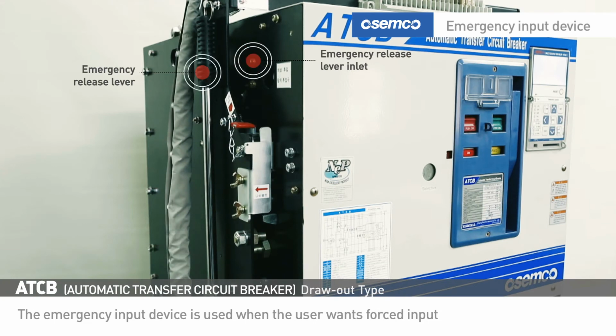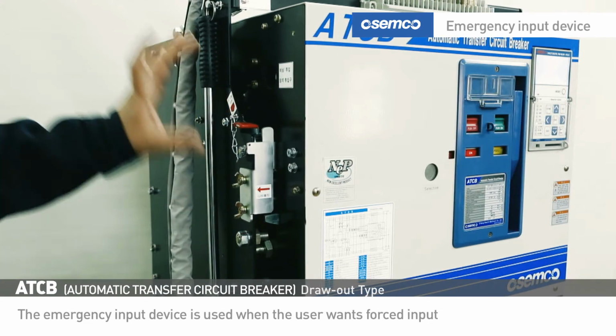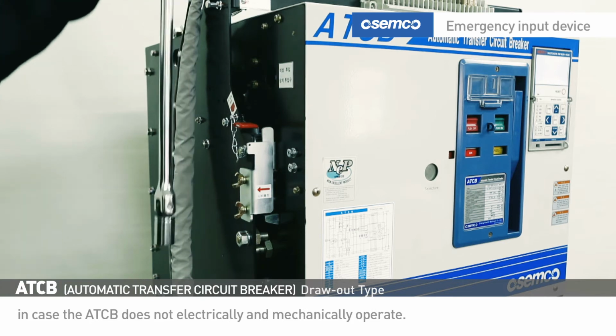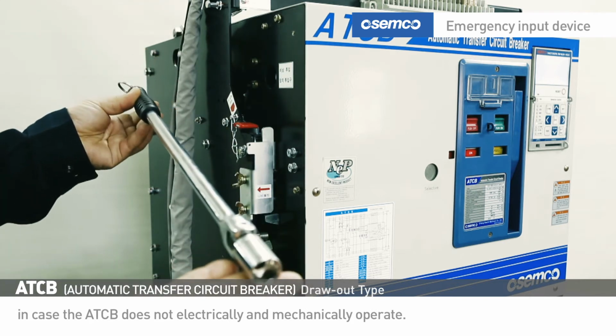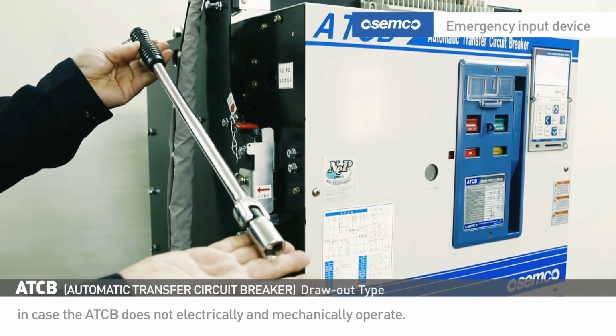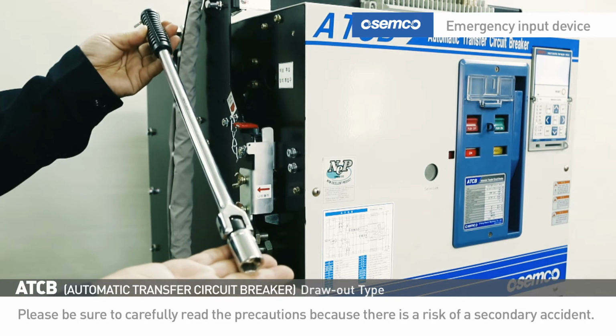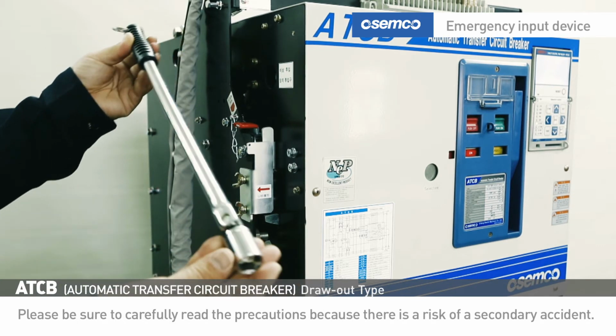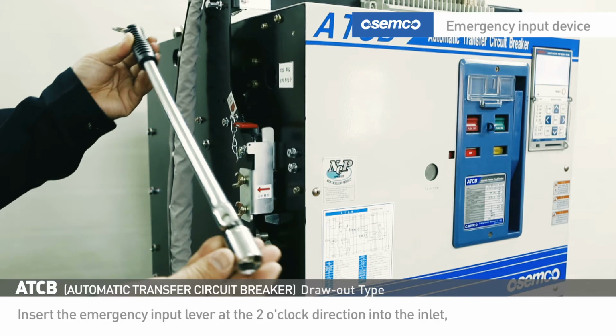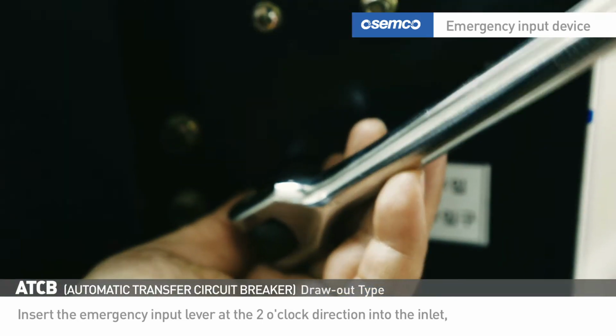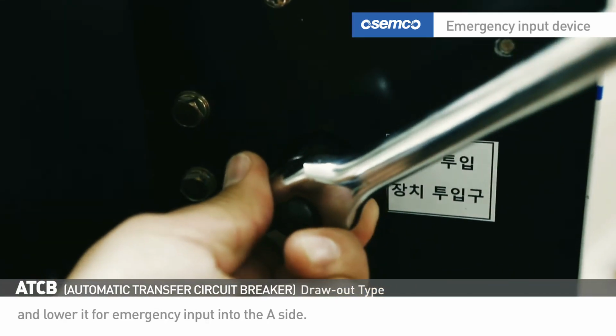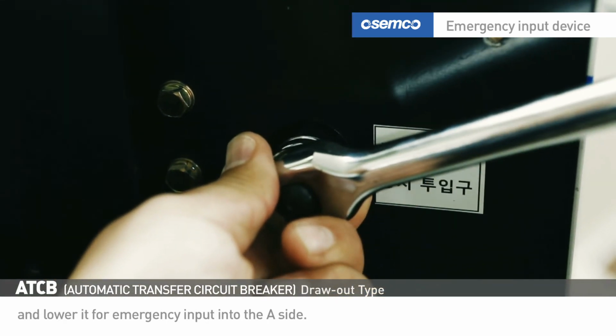The emergency input device is used when the user wants forced input in case the ATCB does not electrically and mechanically operate. Please be sure to carefully read the precautions because there is a risk of a secondary accident. Insert the emergency input lever at the 2 o'clock direction into the inlet and lower it for emergency input into the A side.